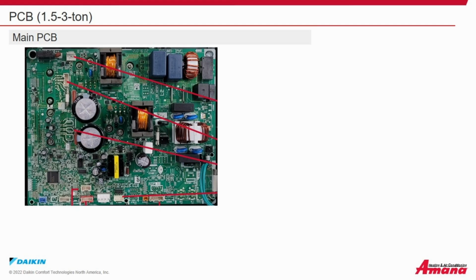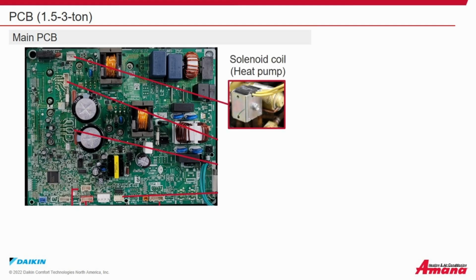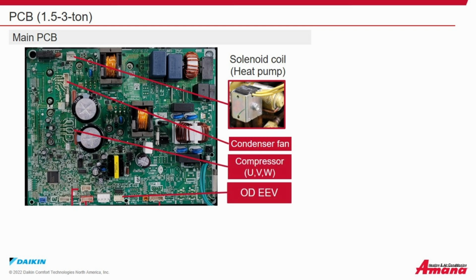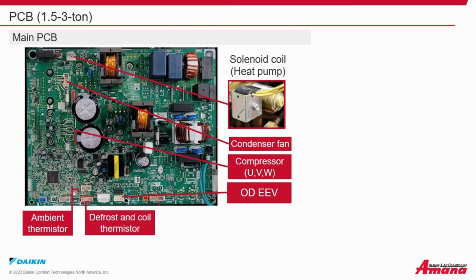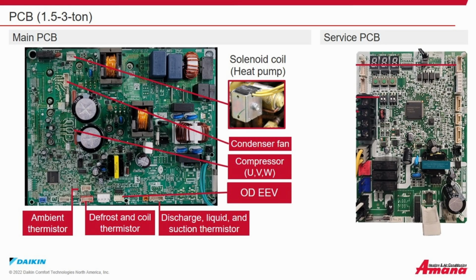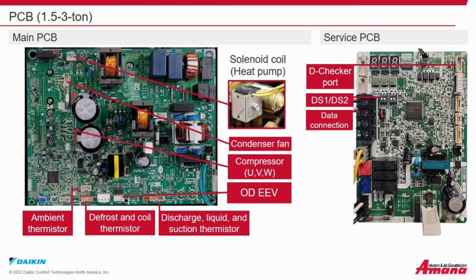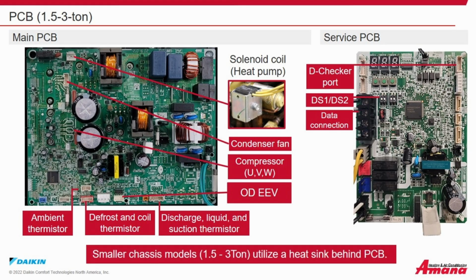Here is the main printed circuit board for a 1.5 to 3 ton unit. This diagram shows the location of the solenoid coil if it's a heat pump, condenser fan, compressor UV and W terminals, outdoor electronic expansion valve, ambient thermistor, defrost and coil temperature thermistor, discharge, liquid, and suction thermistors. On the service PC board, here's the connection for the D checker, the DS1 and DS2 or dip switch 1 and 2, and the data connection. Smaller chassis, the 1.5 to 3 tons, use a heat sink behind the PC board.